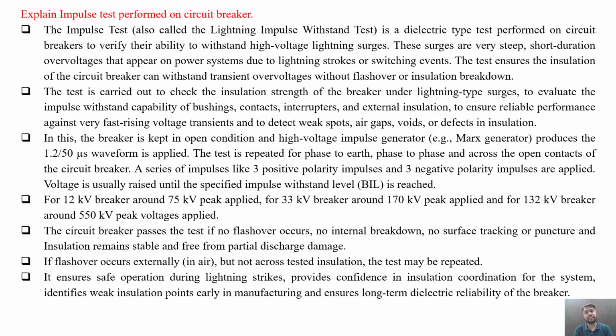The surges are very steep, short duration overvoltages that appear on power systems due to lightning strokes or switching surges. The test ensures that the insulation of the circuit breaker can withstand transient overvoltages without any flashover or insulation breakdown.